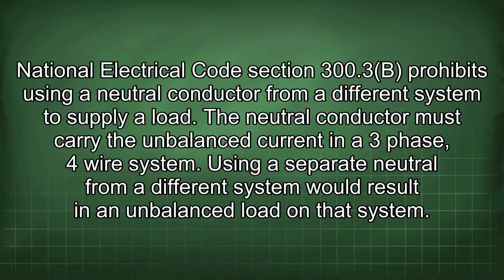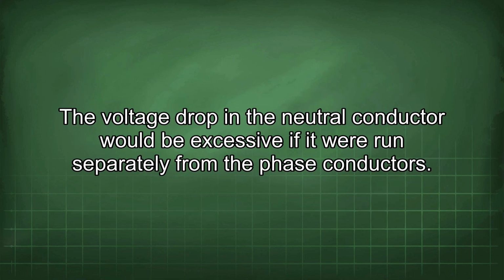National Electrical Code Section 300.3(B) prohibits using a neutral conductor from a different system to supply a load. The neutral conductor must carry the unbalanced current in a 3-phase 4-wire system. Using a separate neutral from a different system would result in an unbalanced load on that system. The voltage drop in the neutral conductor would be excessive if it were run separately from the phase conductors.